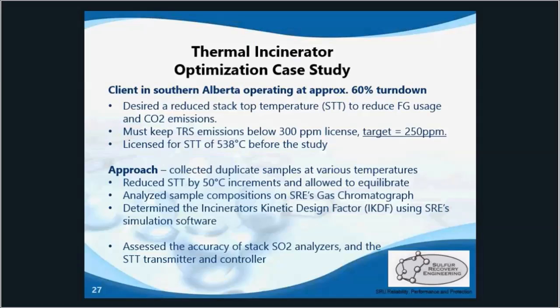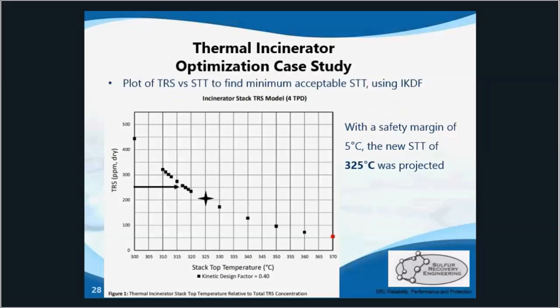We took samples at various temperatures in 50-degree increments, then used those results in our simulation to determine the IKDF. These samples also give us a comparison with the stack analyzers to determine their accuracy. Once we analyzed those samples and put them through the simulation software, that spits out an IKDF — the kinetic design factor — and with that we can develop this curve.